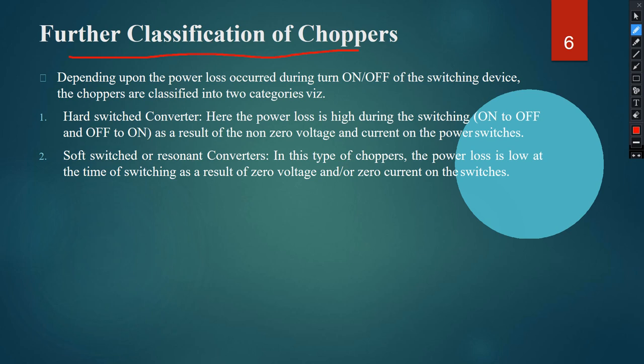Depending on power loss during turn-on and turn-off of the switching device, choppers are classified into two categories. The hard-switched converter has high power loss during switching on-to-off and off-to-on, as a result of non-zero voltage and current on the power switches. The soft-switched or resonance converter has low power loss at the time of switching as a result of zero voltage and/or zero current on the switches.